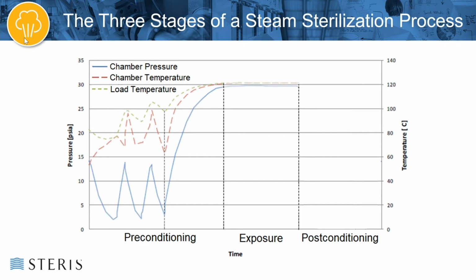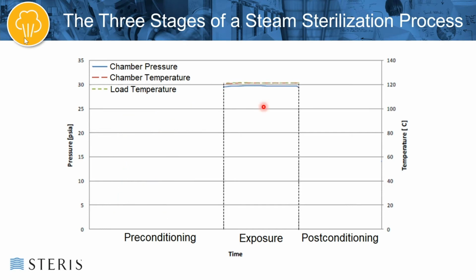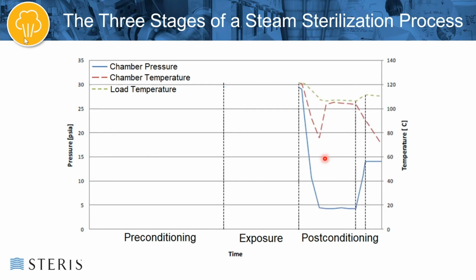Then let's move on to the exposure phase, which is sometimes called a plateau period or a sterilize phase. The chamber pressure, chamber temperature, and load temperature are all in a plateau equilibrium state throughout the duration of the exposure phase. The third phase of the process is post-conditioning, which is broken up into essentially three steps. The pressure drops down, and once it gets below 15 psi, we're talking about vacuum pressures. There's a dwell time down here, which is a vacuum dry time. Then this part is called an air break, where we bring the chamber from vacuum back up to atmospheric conditions, and then the process has ended. So those are the three stages of a steam sterilization process.